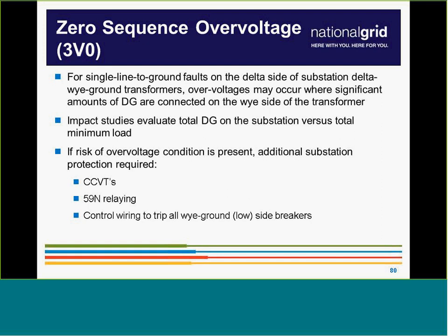When 3V0 is going, how many additional megawatts? Like you talk about how much more you can do. Say 8 megawatts for this. So when it comes to 3V0, as long as you're not overloading your distribution circuits, you're probably not going to have problems until you get close to the transformer nameplate of the substation. So 3V0 is really the big nut to crack. Once that's installed, there is a point where you'll have more generation than the nameplate of the substation transformer, and you need to consider that. But there is a section in there where there may not be significant upgrades to the substation.